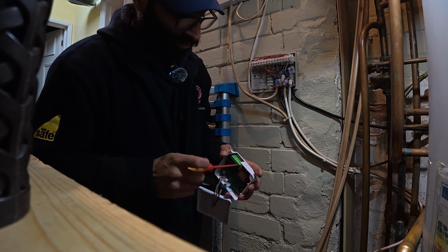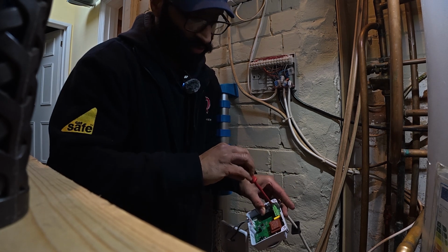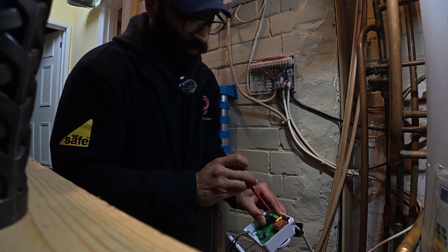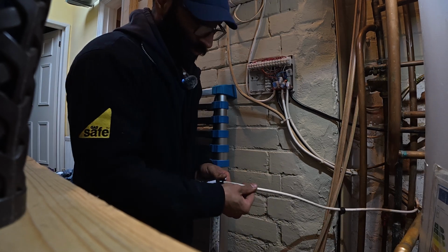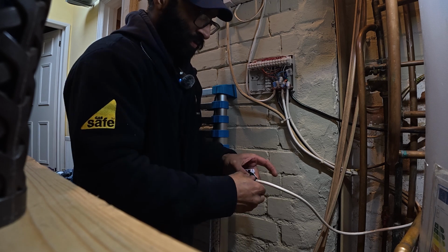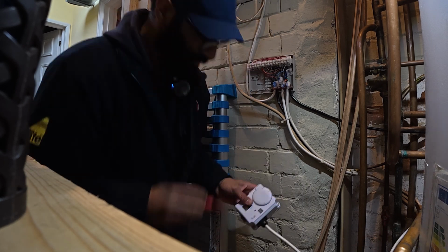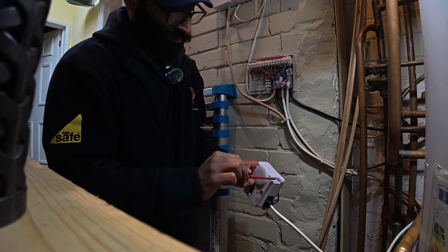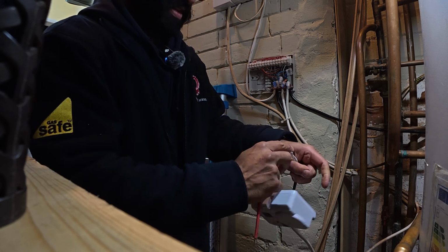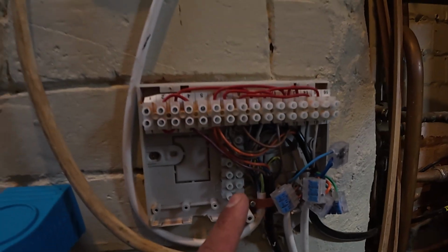All the terminals come closed, so we've got to open them all up. Black into normally open, because that's the one that links to the brown of the zone valve. Grey is common, as that comes from the programmer. And then live and neutral. With a rubber grommet. Slide it up. Push the sensors back into the cylinder, tighten the screws on, so that's on there. That's as I found it.